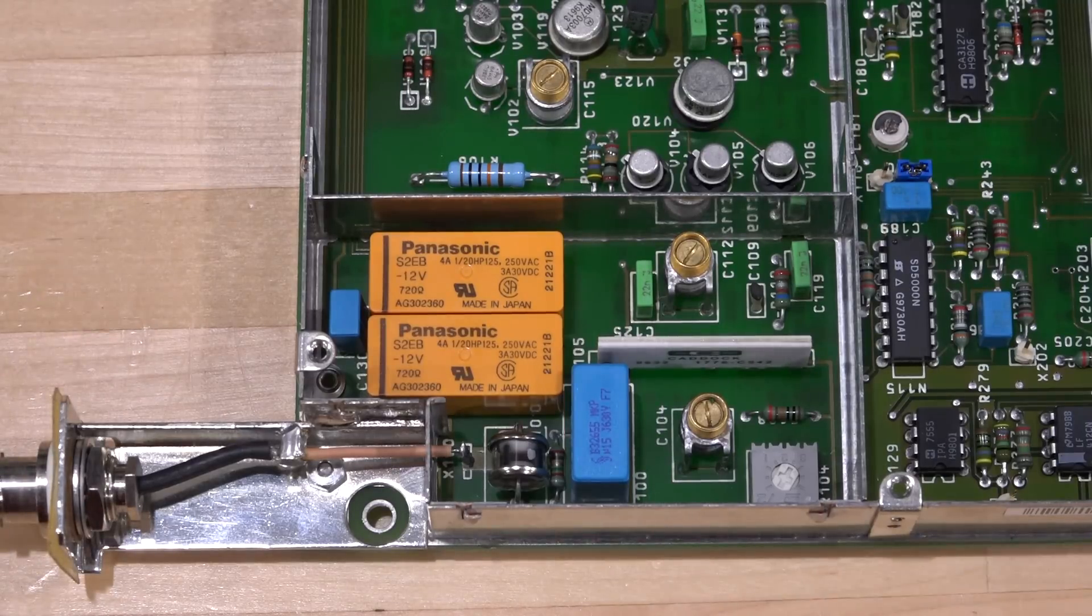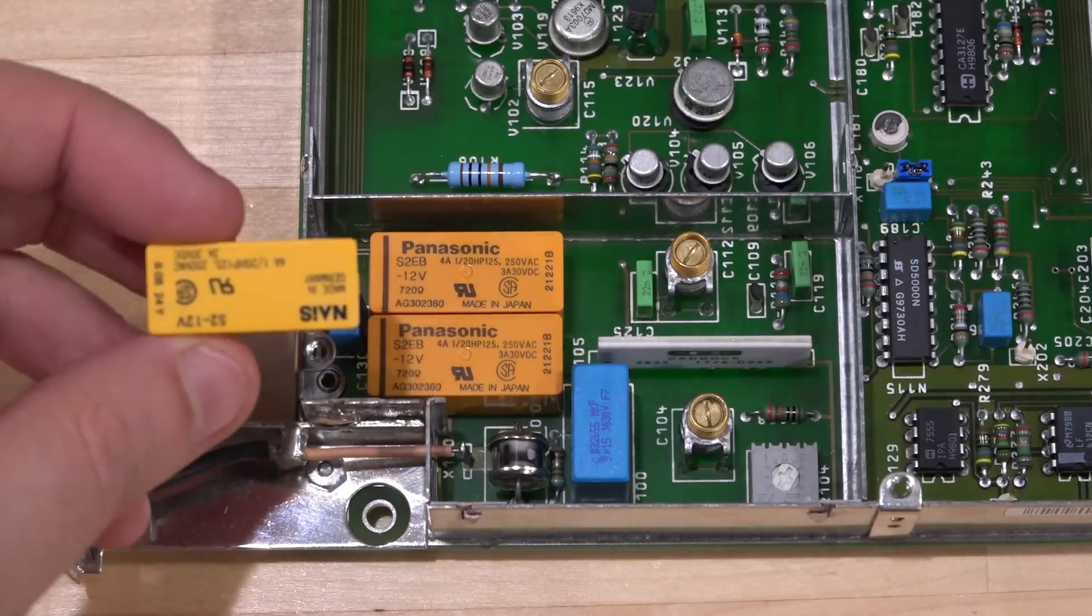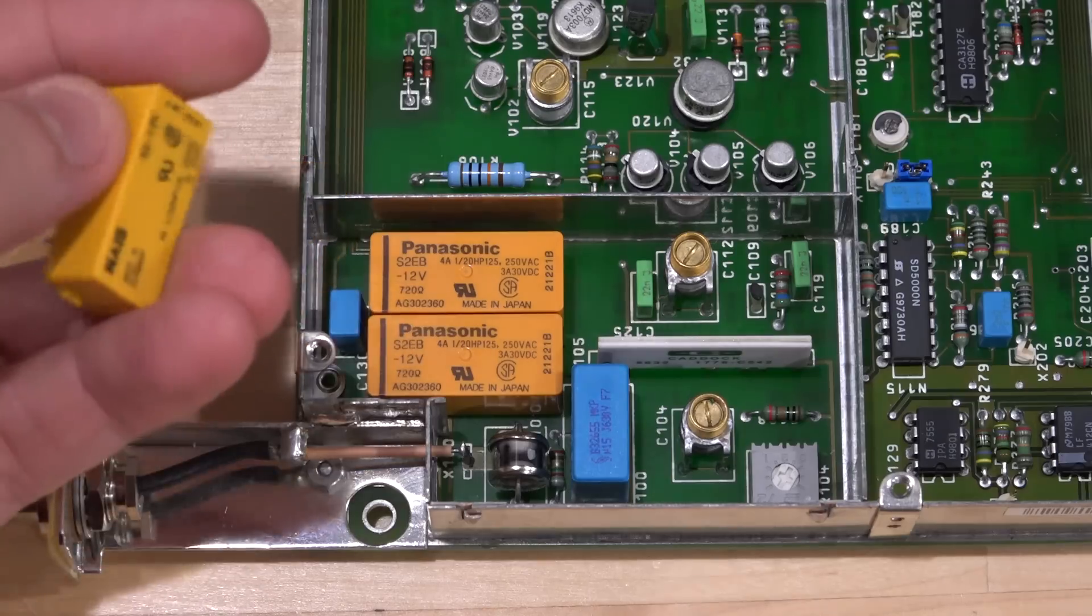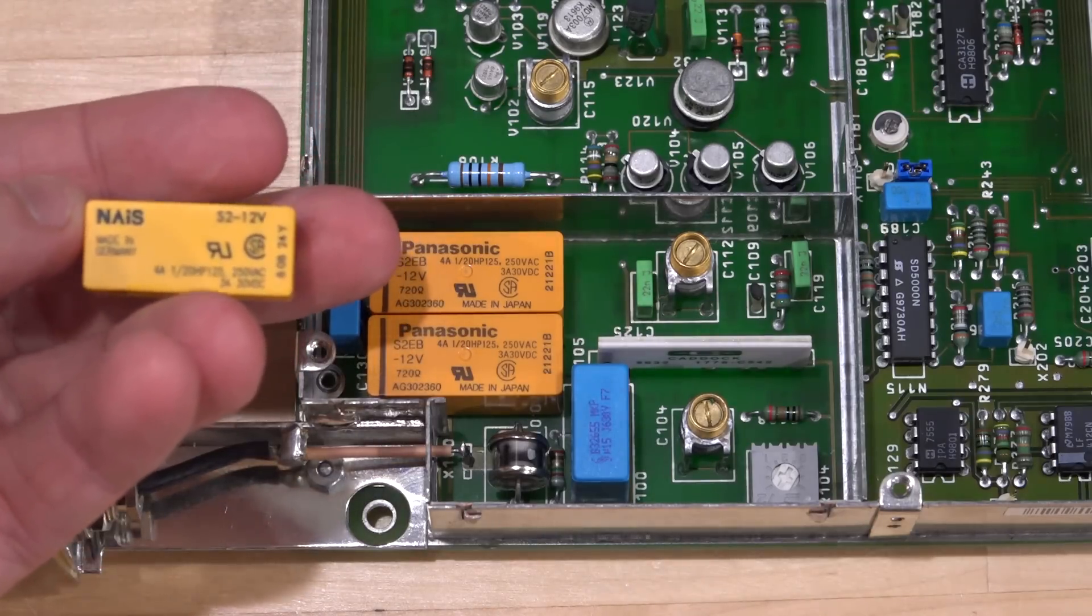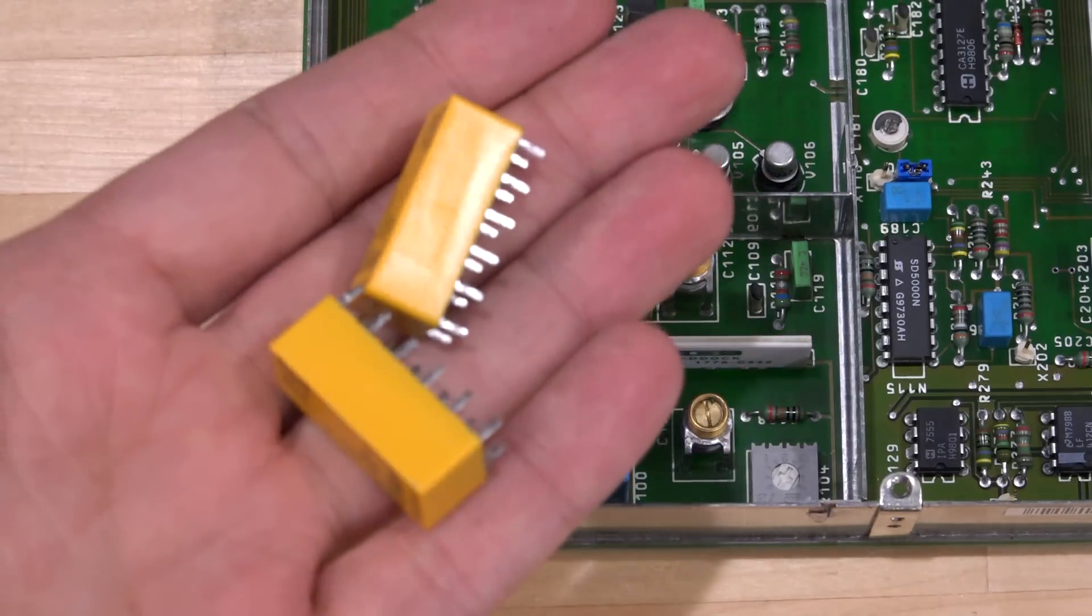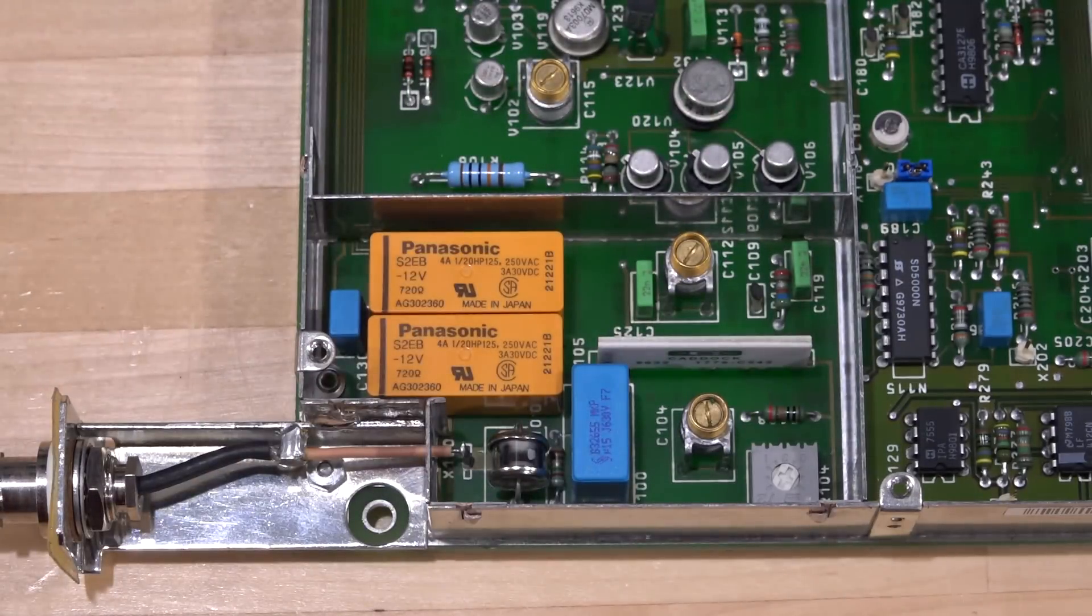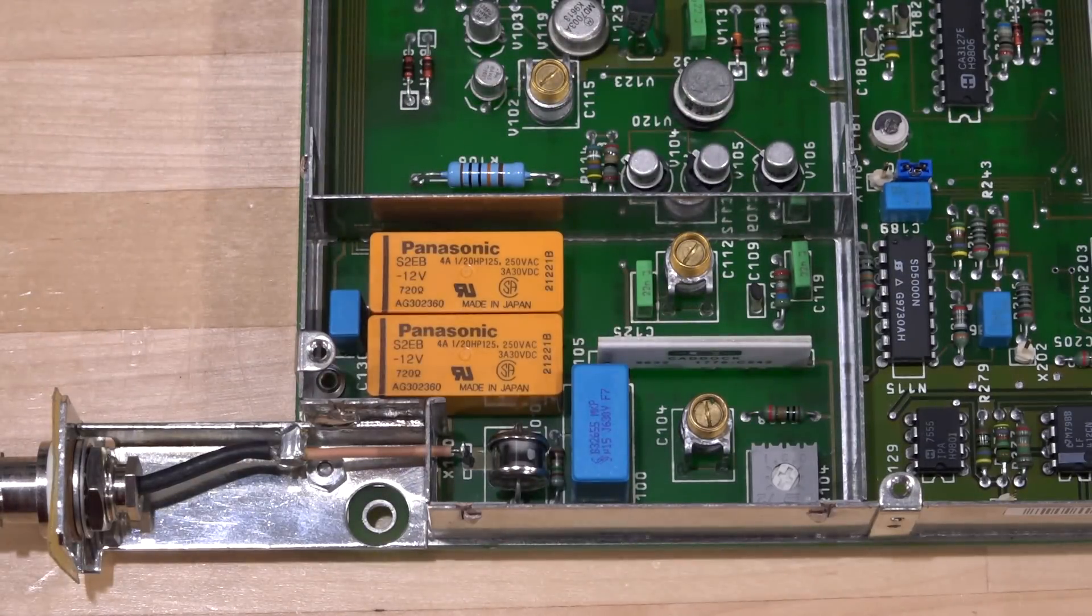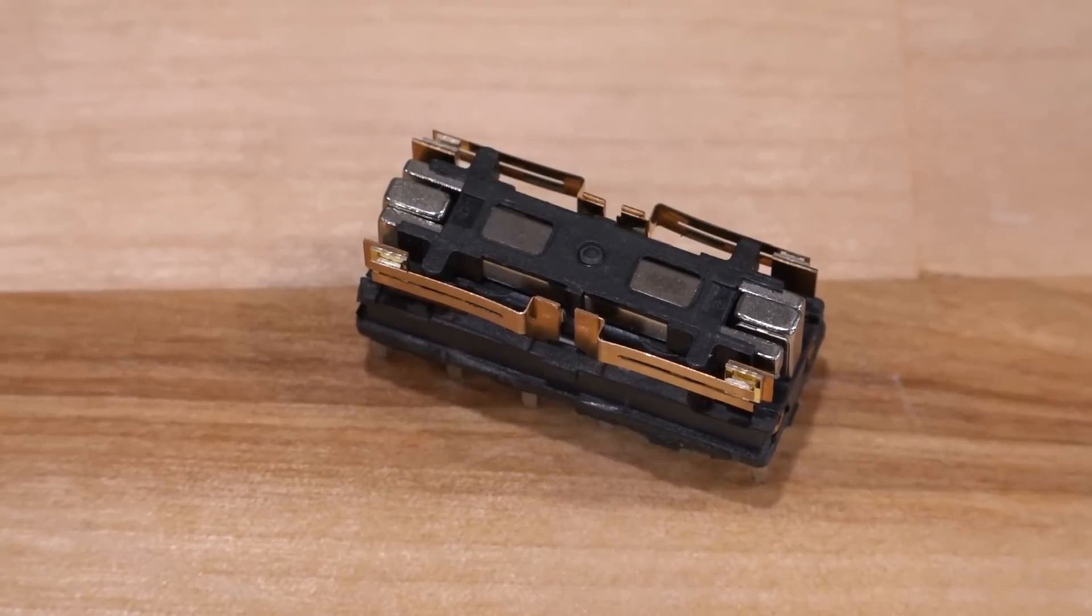I have replaced the two relays at the same time because we want them to be at the same age. Here are the original ones—they were made in Germany. These are Panasonic equivalents made in Japan. I removed two of them at the same time. Let's put it back and see if this solves the issue.